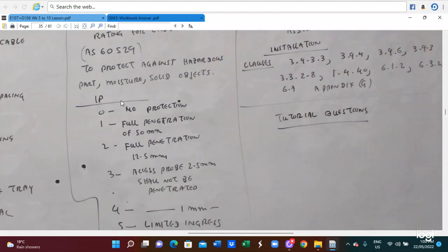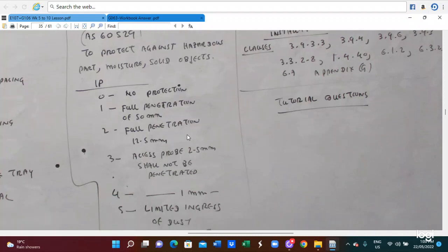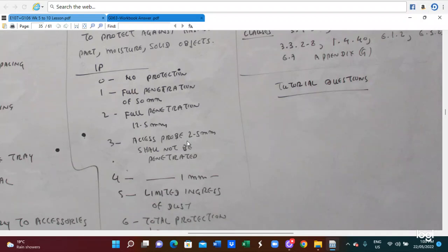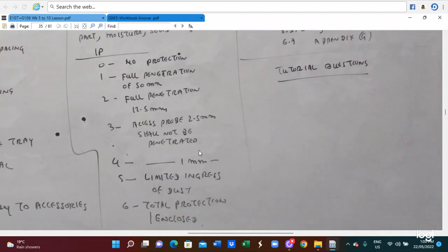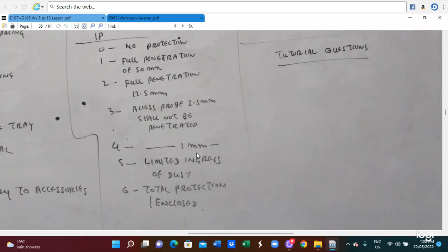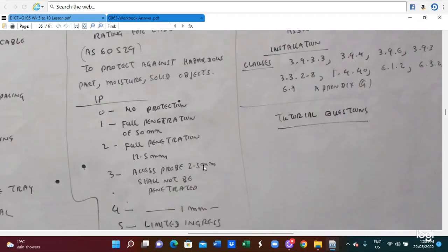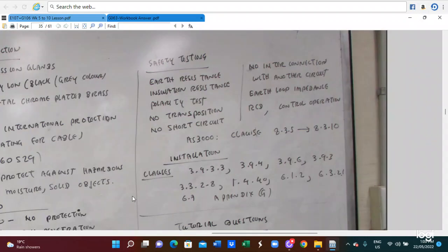So IP0 is no protection, IP1 is full penetration of 50 millimeter, and IP2 is full penetration of 12.5 millimeter, and IP3 is access probes of 2.5 millimeter. IP4 is 1 millimeter. IP5 is limited ingress of dust. And IP6 is total protection against dust. These are the kind of IP protections.